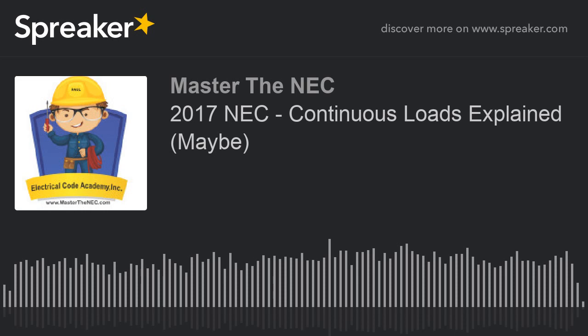Not sure what else to talk about. I guess, again, remember that any load in a commercial building that is going to be 3 hours or more is treated as a continuous load unless the code specifically says that it's not a continuous load. Okay? I am more than sure that I'm forgetting something to express it even better. Hopefully you get a greater understanding of wrapping your head around it.